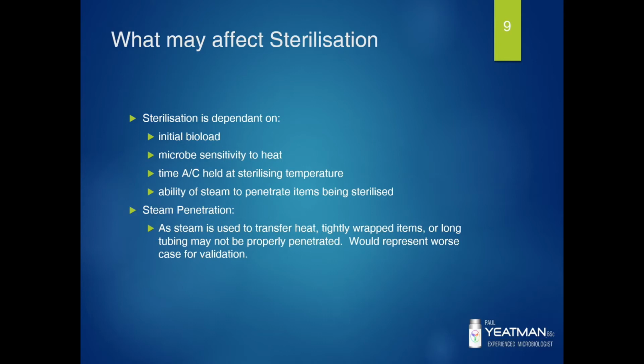So with the bioload, if you validate to kill 100 colony forming units, or CFU, and your initial bioload is 200 CFU, then your sterilisation will not be effective. If you validate using Micrococcus luteus, you'll get different results than when using Geobacillus stearothermophilus, as the microbes have different thermal survival characteristics. For example, typically we want a D-value of about 1.5, and Geobacillus stearothermophilus provides that. Whereas Micrococcus luteus will have a D-value of, making something up, 0.1, just based on how quick it would die if you did expose it to an autoclave.